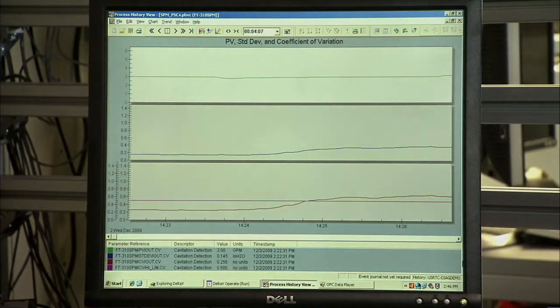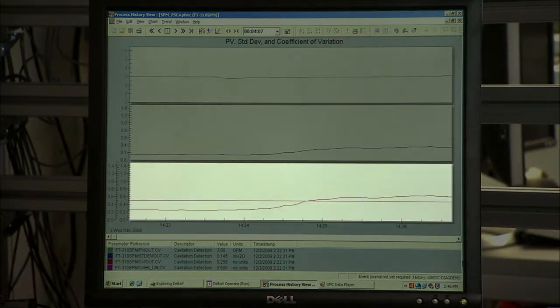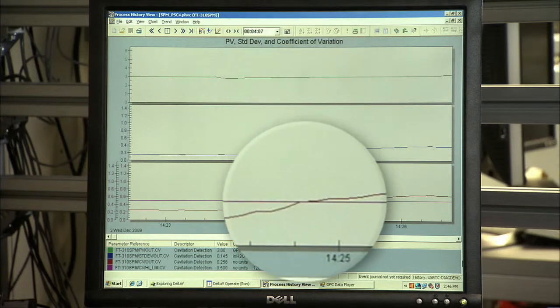Using a data historian, you can see that in addition to measuring the pressure, the 3051S is also measuring the amount of process noise created by the pump. When cavitation occurs, the standard deviation calculated by SPM increases and surpasses this configured threshold.